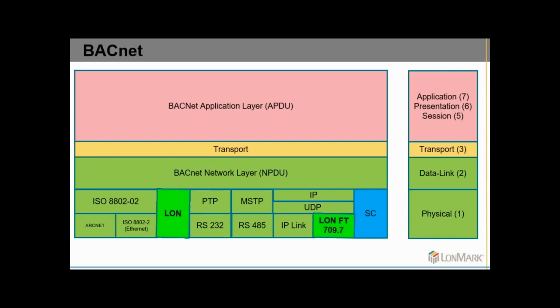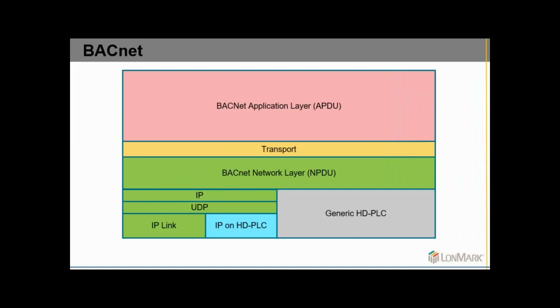So this is a little bit similar to the LON world. You see we have lower layers in BACnet, which refer all to the same NPDU messages. In the past we had a LON layer, which was mainly used by Siemens. We have with 709.7 the opportunity to tunnel BACnet IP messages, UDP messages on a free topology network, and the blue one is new at BACnet. That's a secure communication model which is once again tunneling NPDUs of BACnet through a WebSocket connection. So similar, not as detailed as we have in LON, is a 7-layer OSI model: physical layer, data link, transport, and application layers. So how does HD-PLC fit in here?